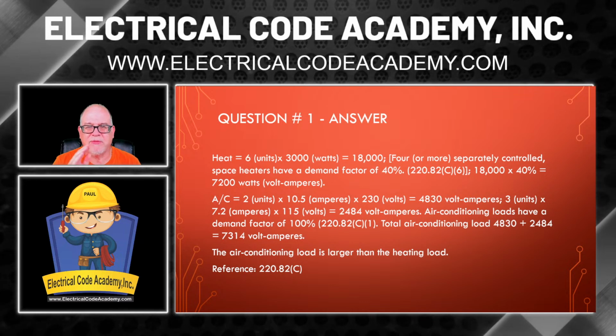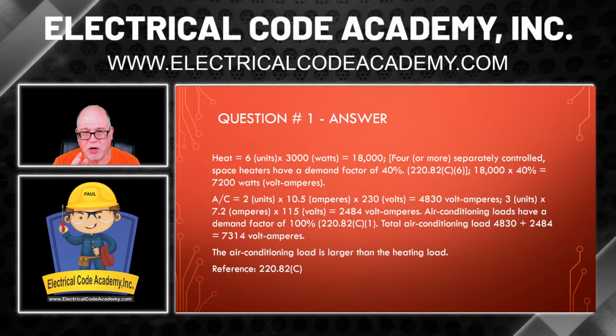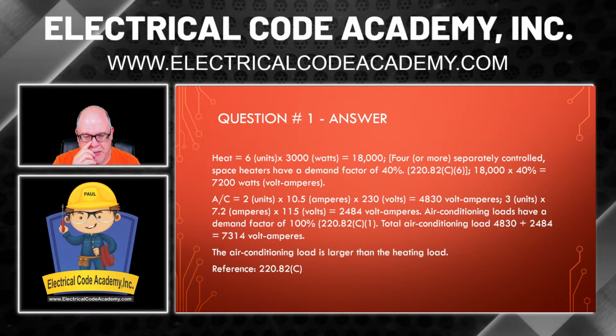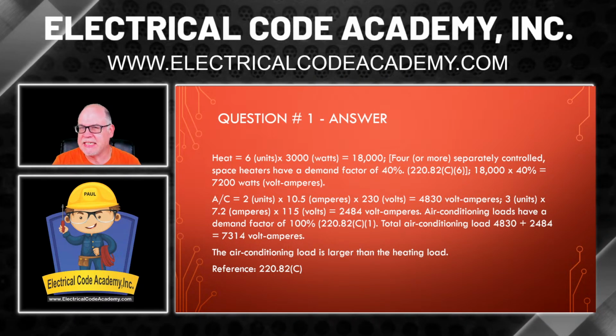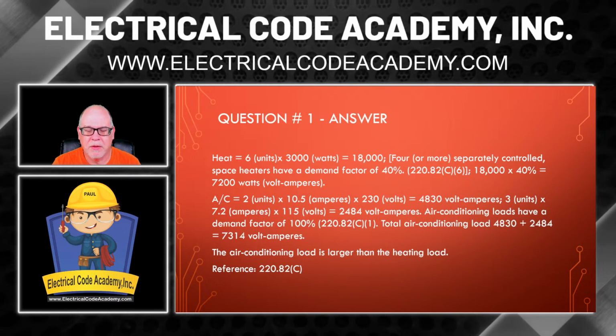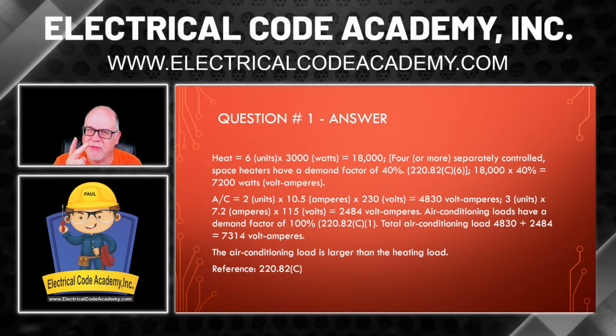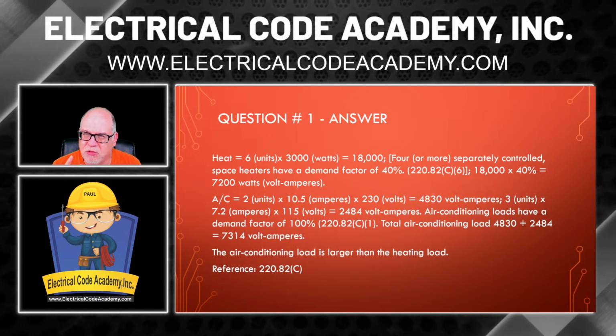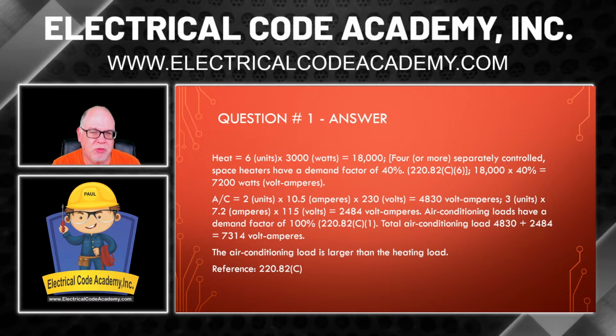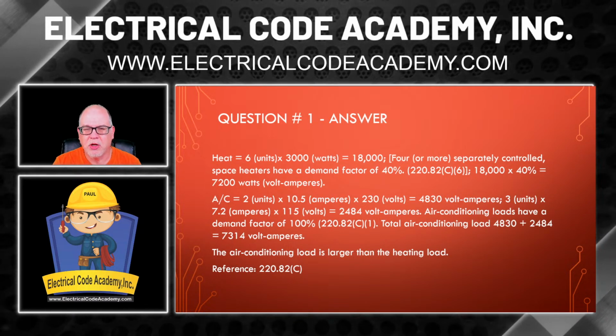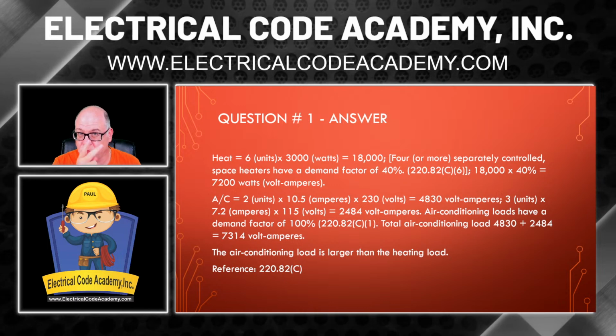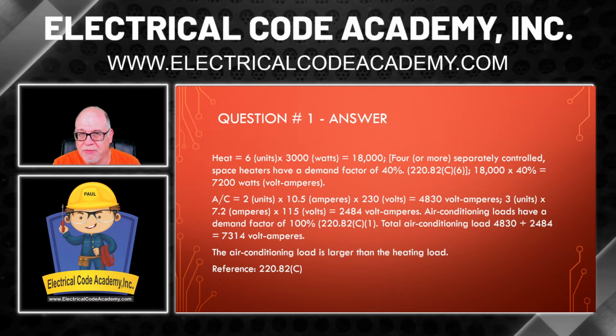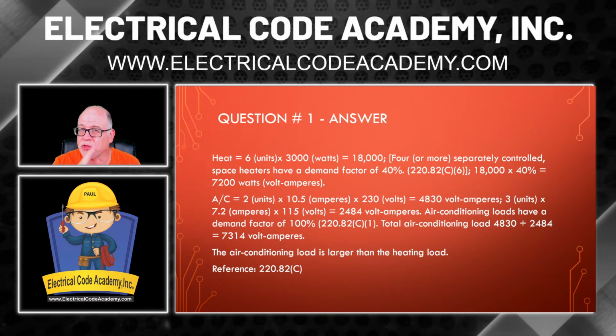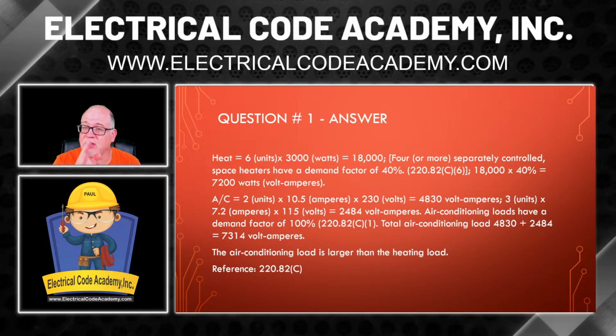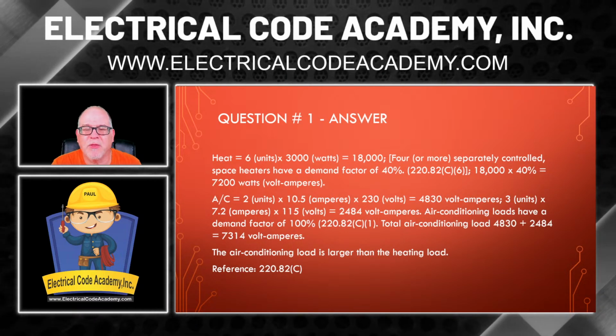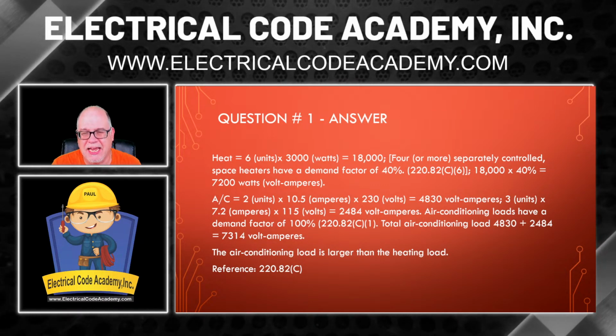Now let's look at that AC, because we know that we've done the heat already, and 7,200 is what we're working with for the heat. Is that going to be greater than the AC? Well, that's what you got to work out. Remember, we had 2 of them at 10.5 amps each, and we had 3 of them at 7.2 amps. So easy math: 2, because there's 2 of them, times 10.5 times 230 volts. Remember, use the voltage that's given in the question. That's going to give us 4,830 VA.